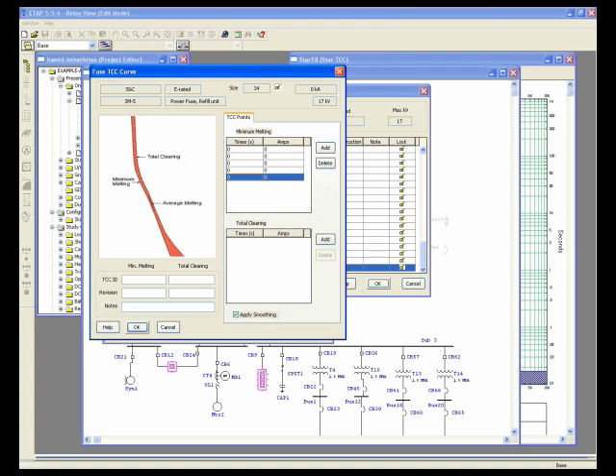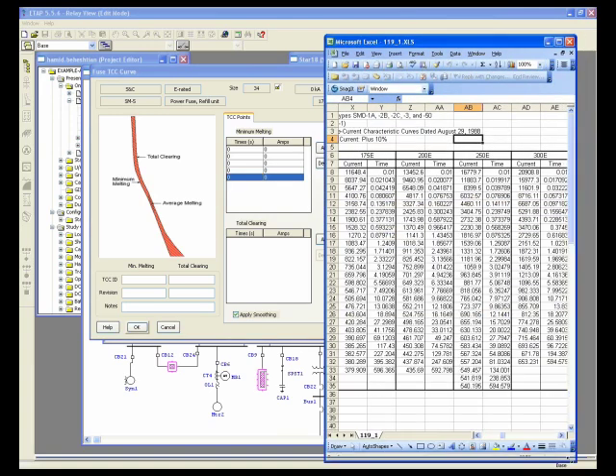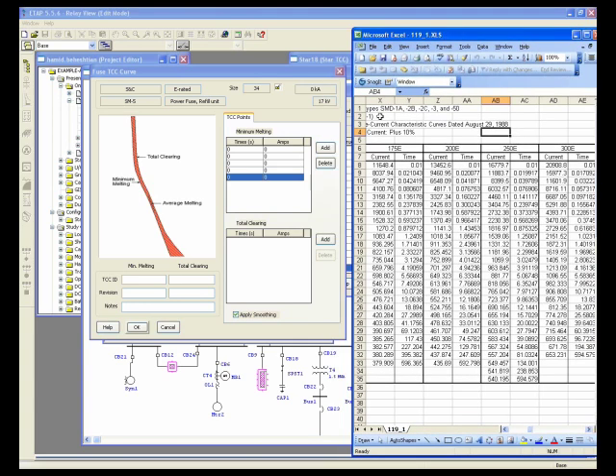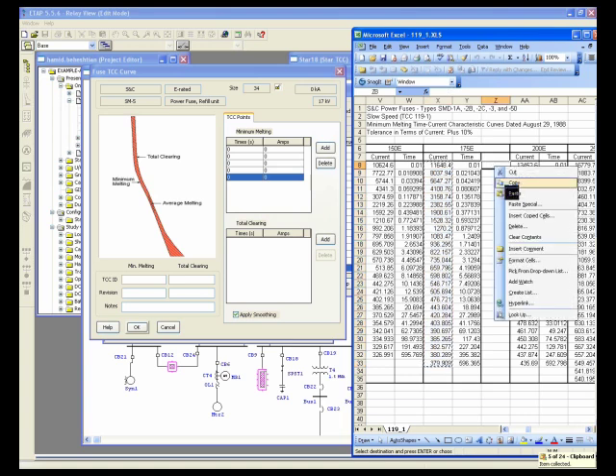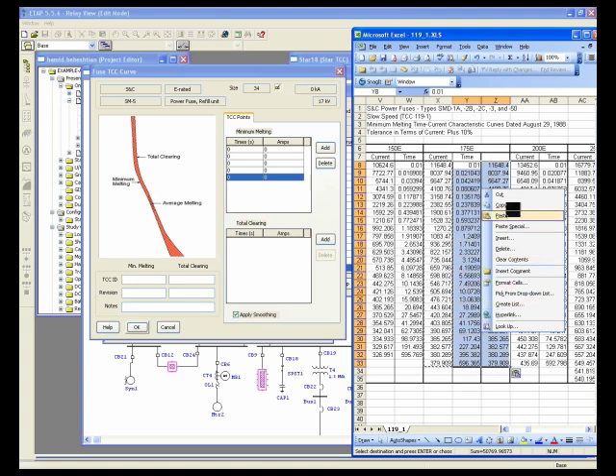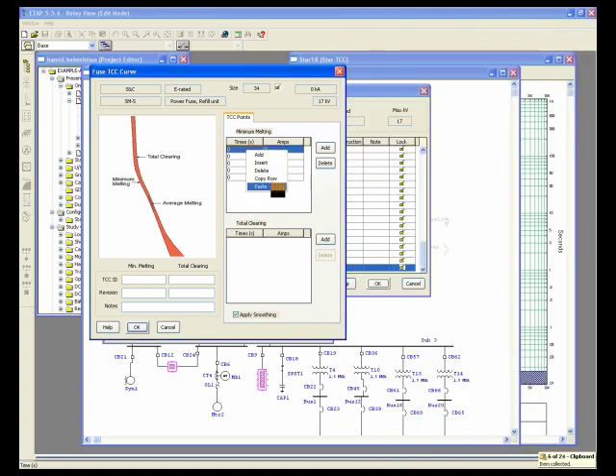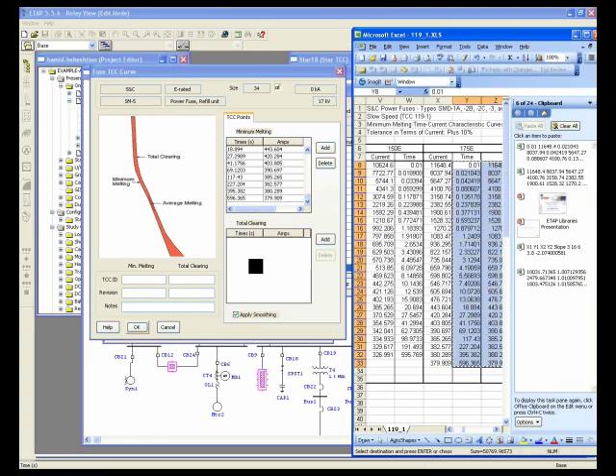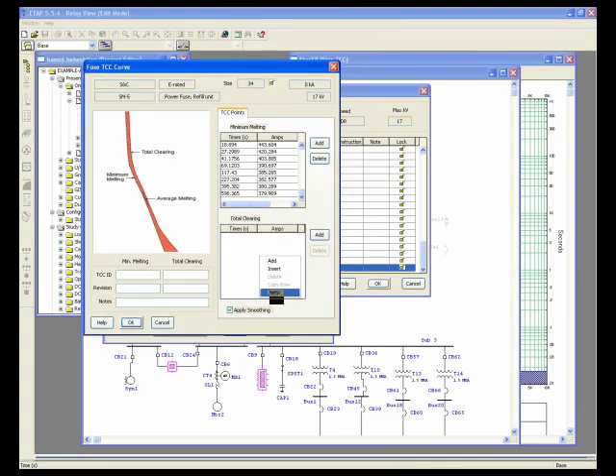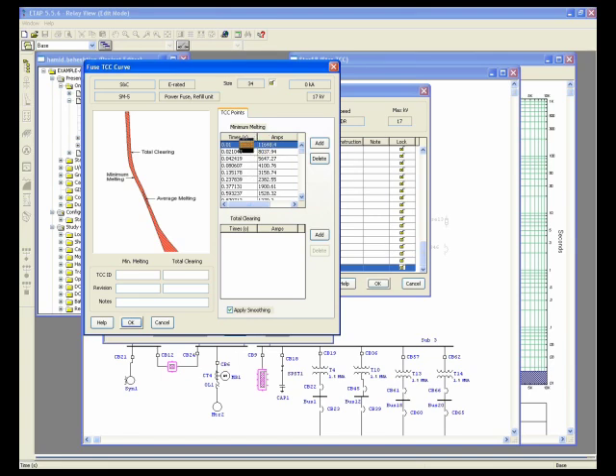Sometimes manufacturers provide these points in Excel format, which is very helpful. If you go to the manufacturer's website, you can find the points in Excel format. When copying and pasting this information into the library, make sure to match the correct columns: the current column in Excel should be pasted into the current column, and the time column into the time column. You can insert rows, copy the current and time data from Excel, then right-click and paste in the ETAP fuse TCC curve editor — it will automatically paste all the TCC points.